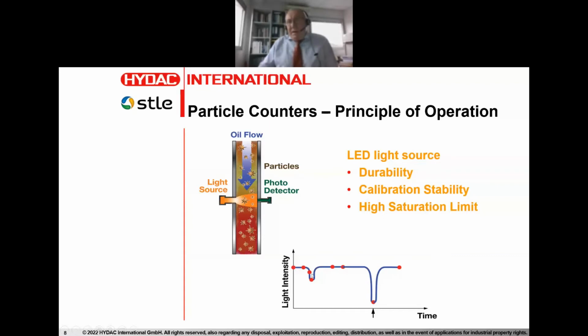So obviously, if there is a small decrease in the light intensity, it's a smaller particle. And if the frequency of these downward peaks is greater, then there are more of them. If there is a big decrease in the light intensity detected by the photodiode, then it means it's a larger particle. And typically what happens is there are fewer of those. On that basis, the particle counter can shuffle them into different bins and determine the particle count for different particle sizes.